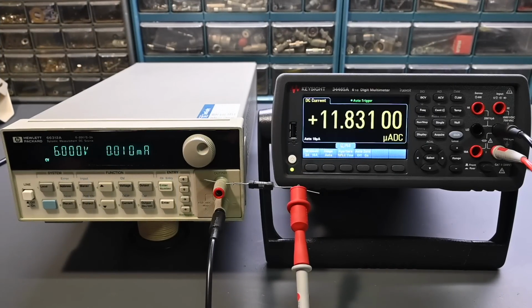So with essentially a short circuit on the power supply's output, it was able to control the constant current mode down to about 800 microamps, as we already saw in the video. Entering values into the power supply to control the current any lower, it just seems to ignore. So 800 microamps seems to be about the limit of the constant current mode. But I was curious about the power supply's ability to measure currents even lower than that.